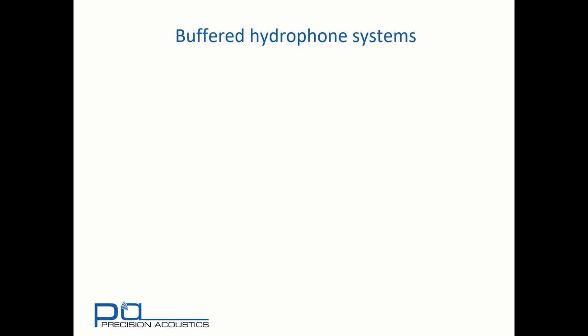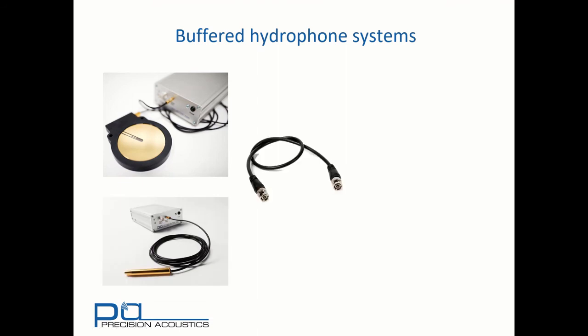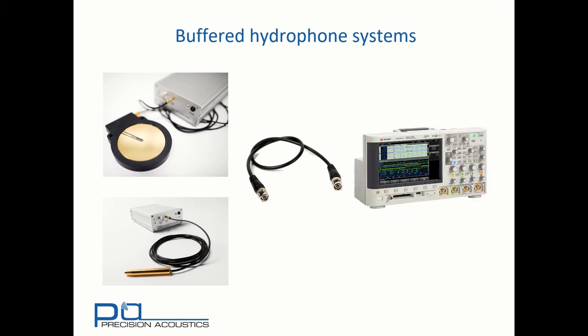So let's have a look at how all of this fits together when we're making hydrophone measurements. If we have a membrane or needle hydrophone which incorporates a preamplifier, then these have 50 ohm outputs. Because they're buffered, we can use a 50 ohm cable to connect to our oscilloscope, which must also always use 50 ohm impedance.